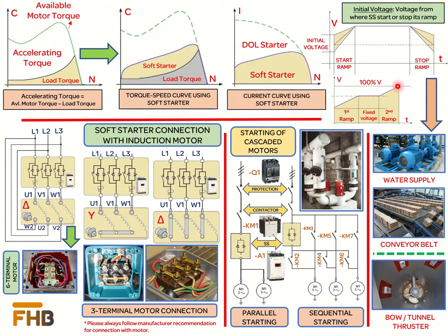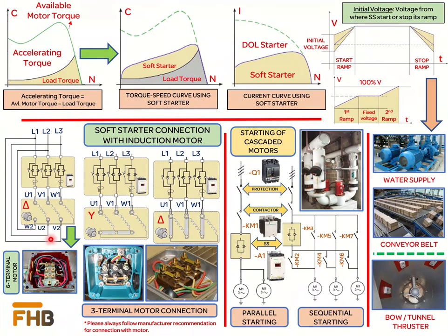We will now discuss about the soft starter connections with the induction motor. There are many ways of connecting the soft starter to the motor terminals. The most used method is the inline connection, where all three phases from the soft starter are connected to the motor terminals as shown in the diagram. Another method is the inside delta connection, shown here. This technique allows the replacement of an existing star delta starter with the soft starter.